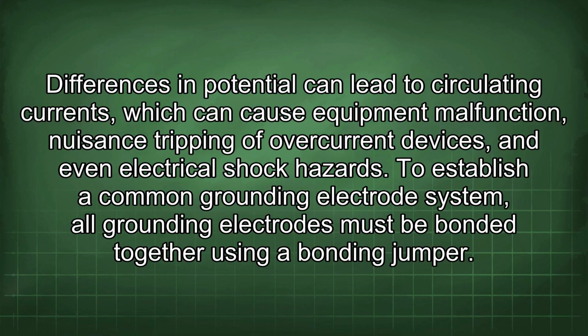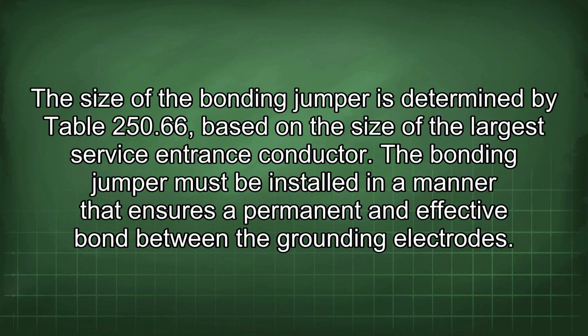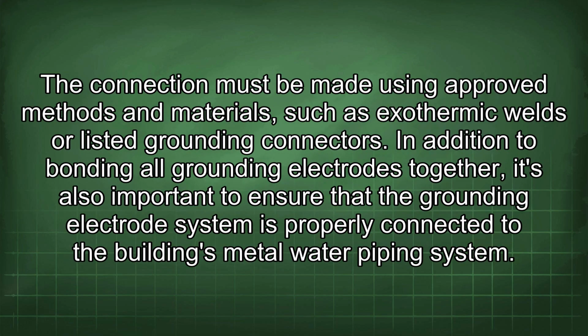To establish a common grounding electrode system, all grounding electrodes must be bonded together using a bonding jumper. The size of the bonding jumper is determined by Table 250.66 based on the size of the largest service entrance conductor. The bonding jumper must be installed in a manner that ensures a permanent and effective bond between the grounding electrodes. The connection must be made using approved methods and materials such as exothermic welds or listed grounding connectors.